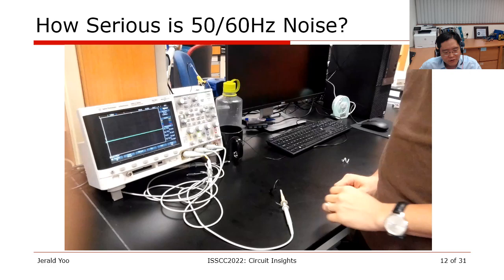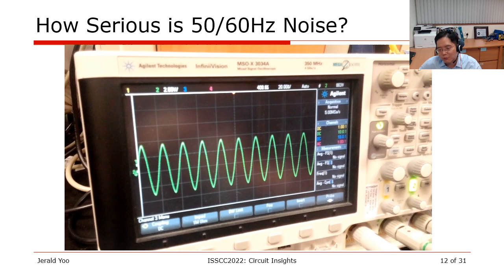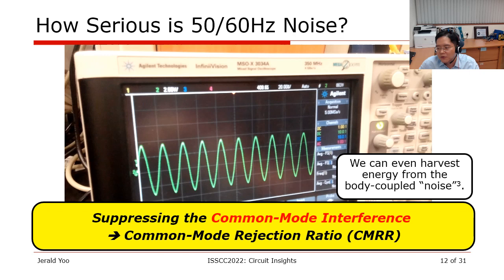I mentioned that 50–60 Hz common mode interference is a big issue in biopotential amplifiers. Here I included an experiment from my lab: I grab the oscilloscope probe with the ground pin floating to replicate a wearable environment. You can see from the oscilloscope screen a nice sine wave of 7-volt peak-to-peak. That's 7 volts, whereas the signal of interest is in the millivolt or microvolt region. This is why we need really high CMRR to suppress the common mode. As a side note, you can even harvest energy from this body-coupled noise because it is so high.